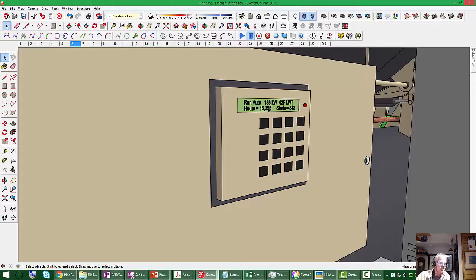Now, it's probably not that heavily loaded, because at part load, if you know about chiller performance curves, there's actually a sweet spot at a part load condition. So the half kW per ton full load figure is probably high for the part load condition. But one thing you could conclude is, well, this machine's certainly got a load on it. Probably not 300 tons, but it's got a load on it, right?